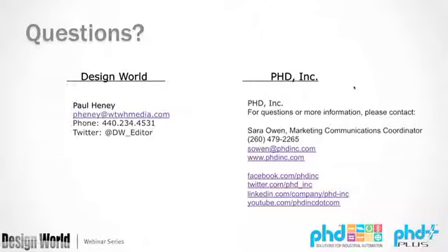Fair enough. Someone asked, why not compare pneumatics against electromechanical solenoids, and wouldn't this be more on the same level? Well, the electromechanical solenoids that I'm aware of are very small. They have low thrusts, very short strokes, and low duty cycles. They will overheat over time. The actuators that we're speaking about, or at least the ones we have the most experience with, are large actuators. We're talking strokes up to a meter in length, and some very large thrusts. So it's a different scale of product, and that's why I didn't address solenoids as a solution in the scope of this presentation.